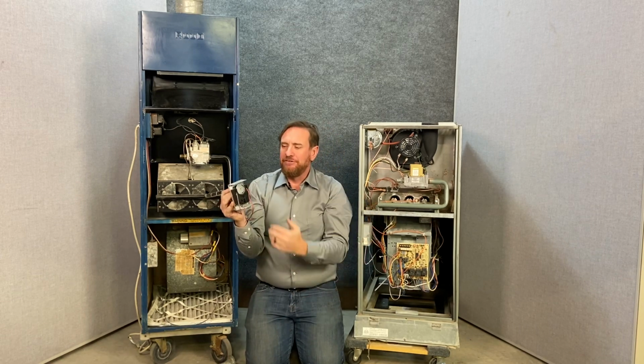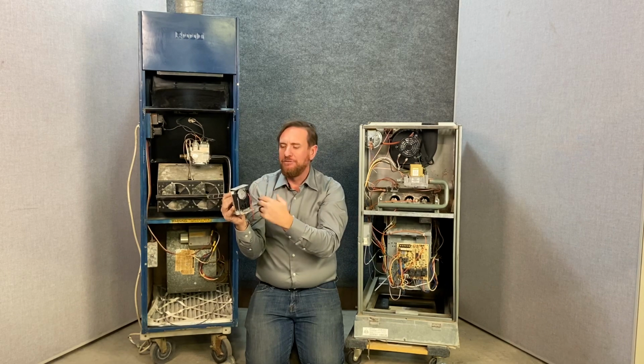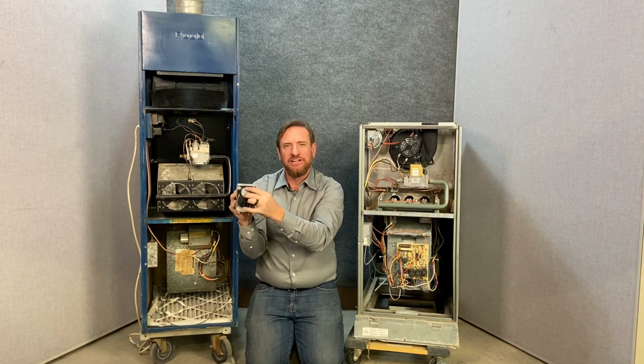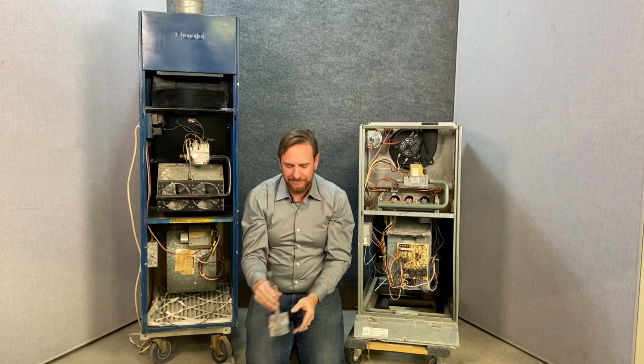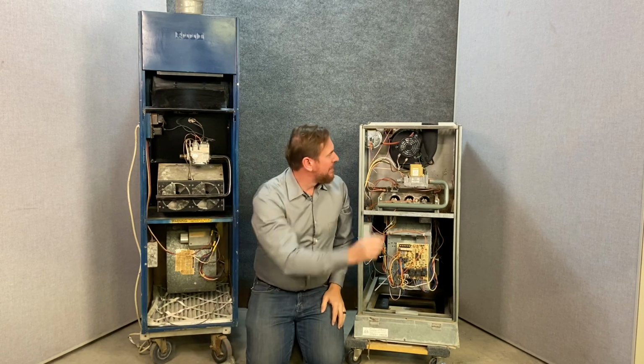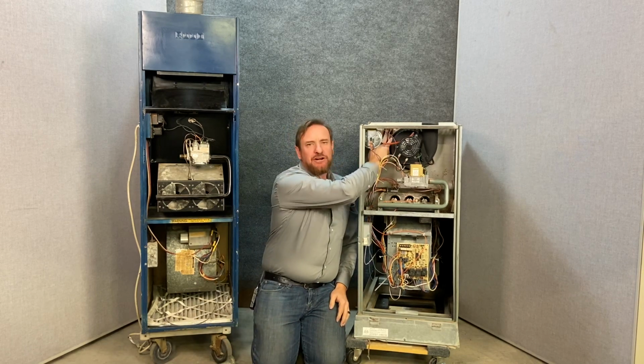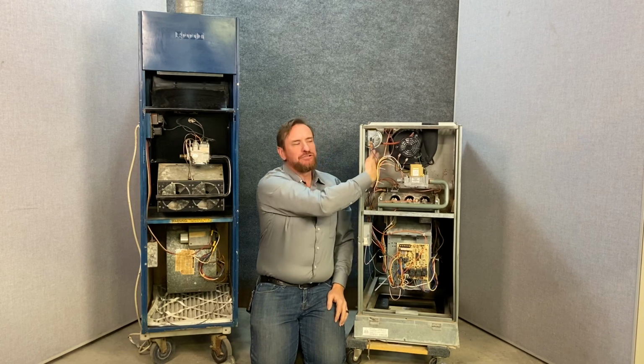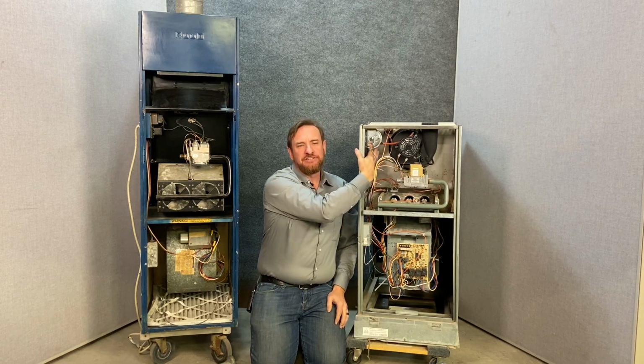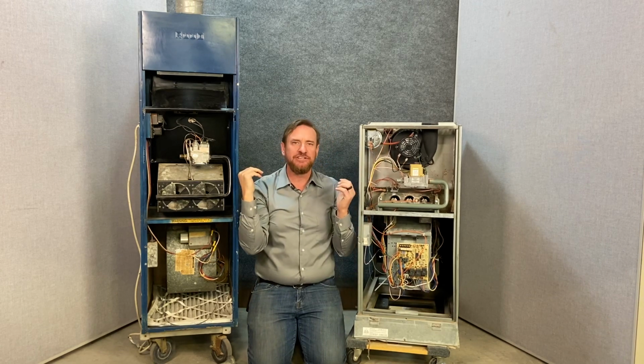With this one, if it was to overheat or have too much heat in there, if it continued to turn, this would shut off the combination gas valve. On this system here, we have a limit switch up in the far right-hand corner. It's just a bimetal switch. If it gets too hot, it shuts the furnace off. So as far as it getting too hot, it shuts the furnace off.